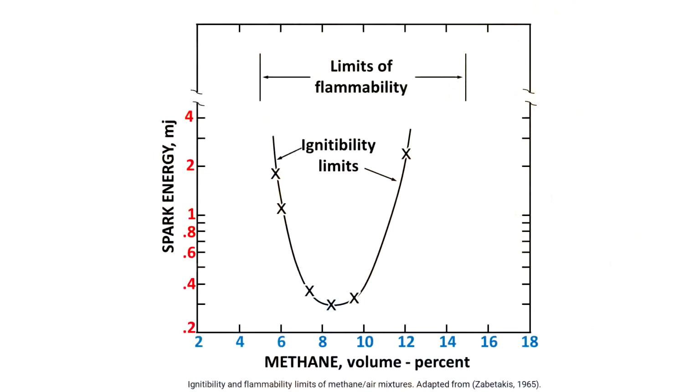The concentration actually determines the minimum ignition energy necessary to actually trigger the combustion. The closer you are to the outer limits of that combustion range, the more energy that's required. And then beyond those limits, of course, there simply isn't enough energy typically to get them to ignite at all.